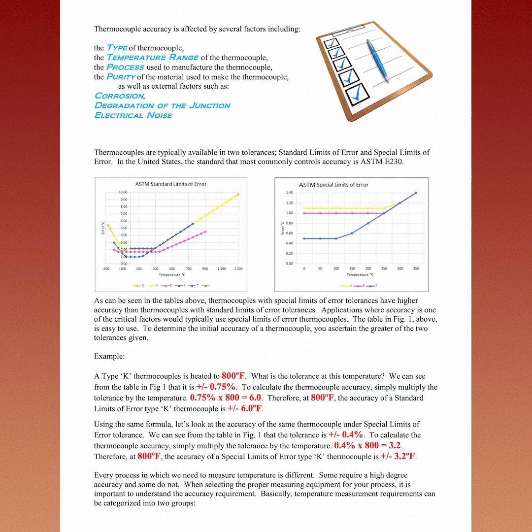Using the same formula, let's look at the accuracy of the same thermocouple under special limits of error tolerance. We can see from the table in Figure 1 that the tolerance is plus or minus 0.4%. To calculate the thermocouple accuracy, simply multiply the tolerance by the temperature. 0.4% times 800 equals 3.2. Therefore, at 800 degrees Fahrenheit, the accuracy of a special limits of error type K thermocouple is plus or minus 3.2 degrees Fahrenheit. Every process in which we need to measure temperature is different.